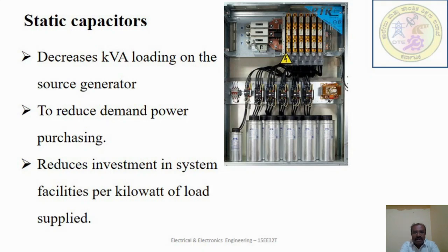The main disadvantage is they have short service life ranging from 8 to 10 years, and they are easily damaged if the voltage exceeds the rated value. Once the capacitor is damaged, it should be replaced, and their repair is uneconomical. You can see in a diagram the capacitors are placed to improve the power factor. The disadvantage is if the capacitor is damaged, it should be replaced.